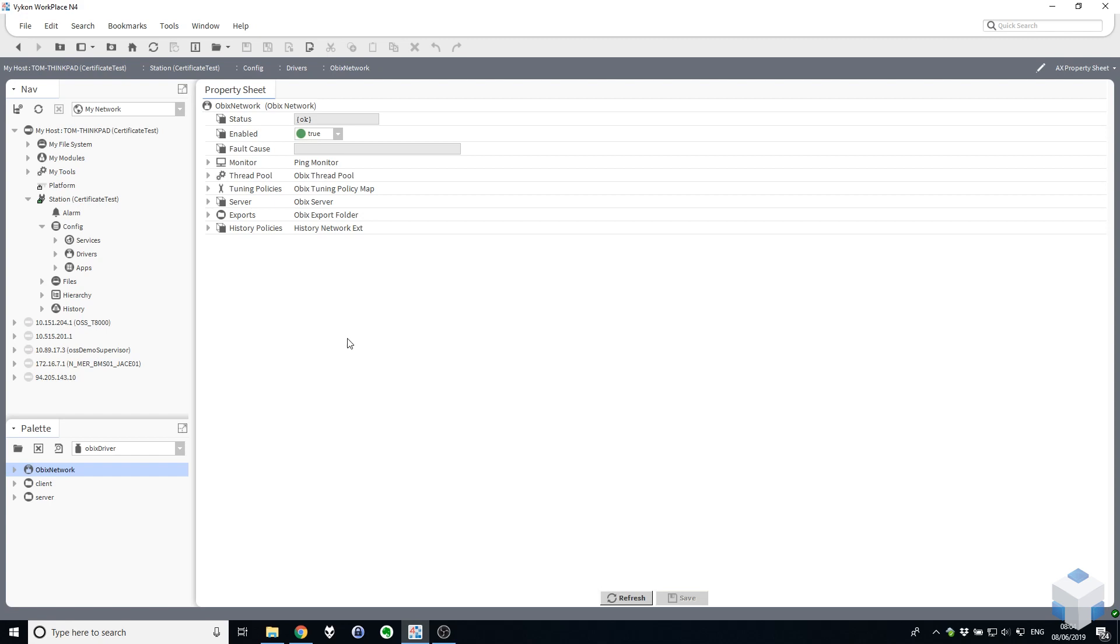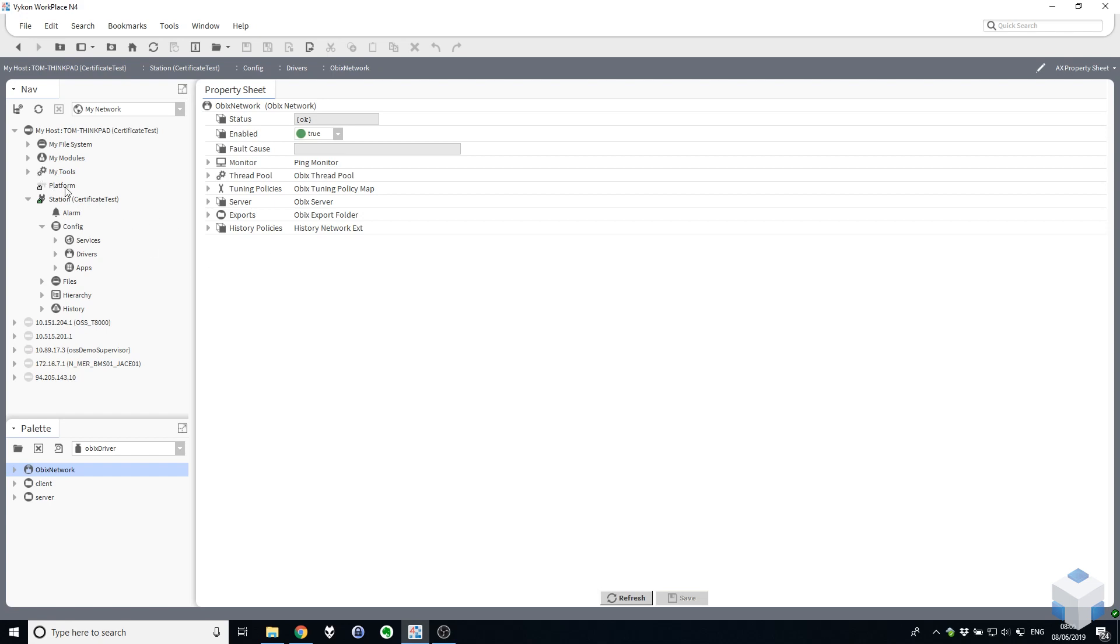However, programmatically in systems that are using the OBIX protocol over HTTP, there is no option for you to click ignore or a lot of client applications don't provide the button to ignore certificates and quite rightly so because certificates and HTTPS aim to provide a level of authentication and validity against what you're connecting to. So, I can confirm that OBIX in Niagara 4 does completely and fully support HTTPS if you're using a properly signed and trusted certificate such as I am in this station.